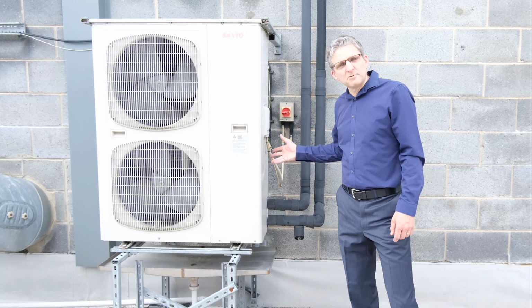Inside this box also, inside the unit, is the compressor and the condenser, which is another heat exchanger that allows the heat to be recovered and it's exchanged into these pipes, where it's sent into the building into underfloor heating pipework and radiator pipework to heat up the building. This particular unit is supplied with electricity and produces hot water or heating hot water. All the components of the refrigeration system are inside the one box, so it's called a monoblock system.